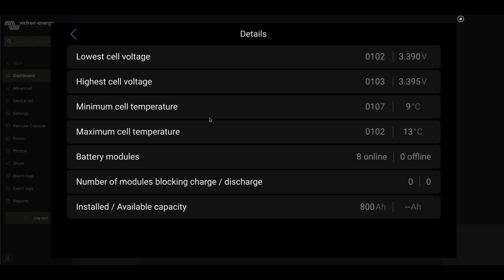Minimum and maximum cell temperature. These are fairly close. What's likely happening here is this 9-degree cell is probably lower down in the bank. A lot of heat that's generated in the bank storage may be rising, so this battery is probably one of the ones on the top. Maybe this battery is low down and on an external wall. This can be a place to go look if you're getting cell imbalance issues or battery balance issues. Is one of these batteries getting too cold?